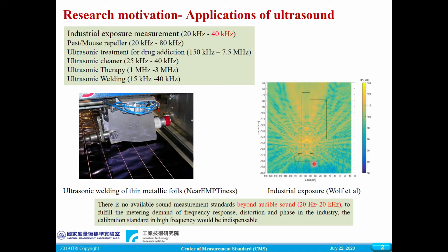And here we are not discussing the unproven effect of high-frequency sound on our health. But this fact means we are exposed to this invisible sound, for there is no sound meter calibrated for the ultrasound frequency range. Therefore, a measurement standard for this high-frequency sound will be necessary. This research is mainly confirming the free field calibration of microphone sensitivity in 20 kHz to 40 kHz in order to expand the CMC.